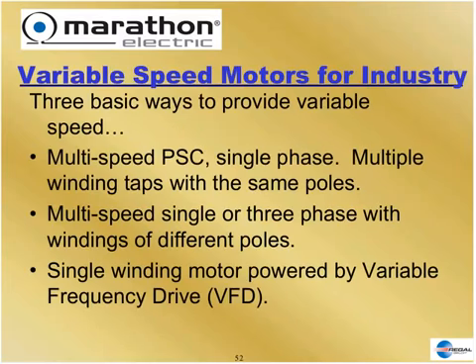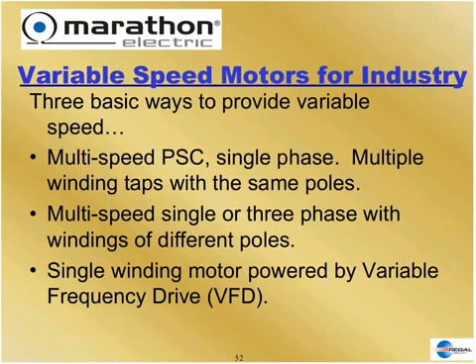Now what if a customer wants variable speed? There are three things that determine motor speed: frequency, number of poles, and amount of slip. With a fixed number of poles, a fixed amount of slip, and utility-supplied frequency, you'll only have a one-speed motor. For fan loads, we build multi-speed PSC single-phase motors with multiple speed taps. The taps strengthen or weaken the motor, changing the slip to run faster or slower — like a ceiling fan where pulling the chain gives you medium, then low speed.